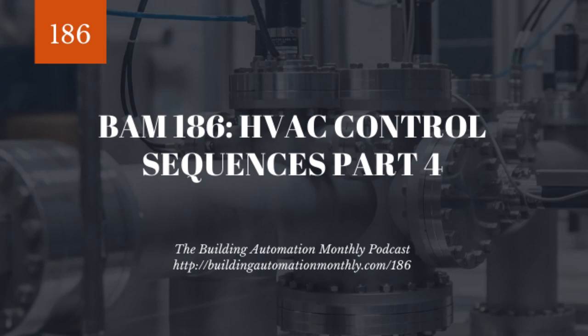So with face and bypass, what that is, you have a damper that faces the coil and a damper that bypasses the coil. So bypassing would just straight up continue the airstream through this little dip. Typically, it'll go either up or down, and it'll be a bank of dampers. The top one will open up and will face the coil and allow you to go through the coil. Sometimes it's the bottom one that will face the coil. It just depends how the unit's built. And then the bypass damper, whichever damper that is, opens up to bypass the coil.